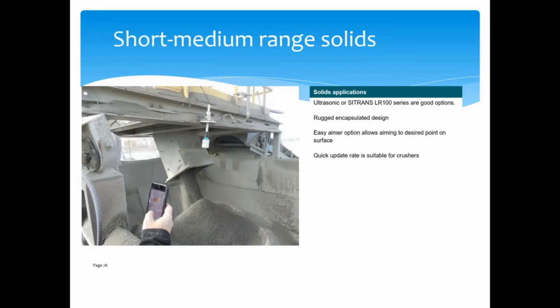If you're dealing with short or medium range solids, again, high frequency radar is probably the best way to go for all the reasons we talked about today: narrow beam angle, the ability to aim it to deal with the angle, and quick response time.